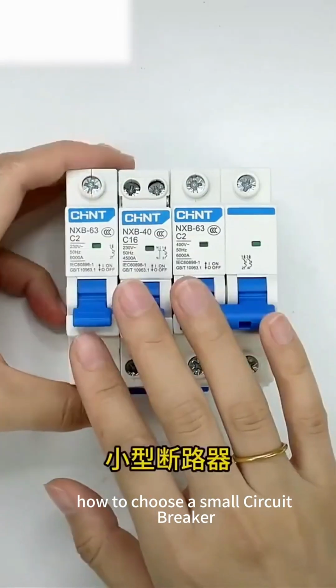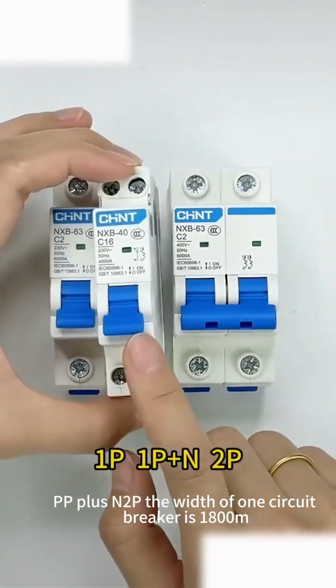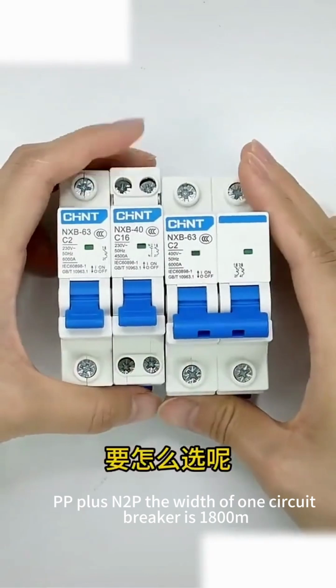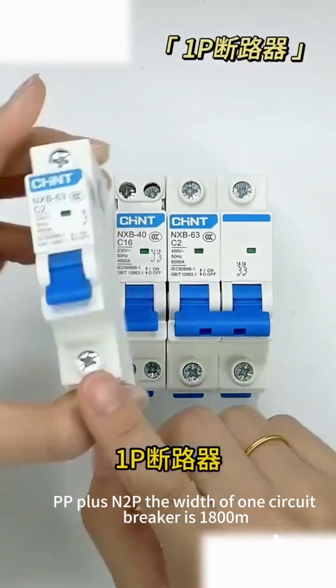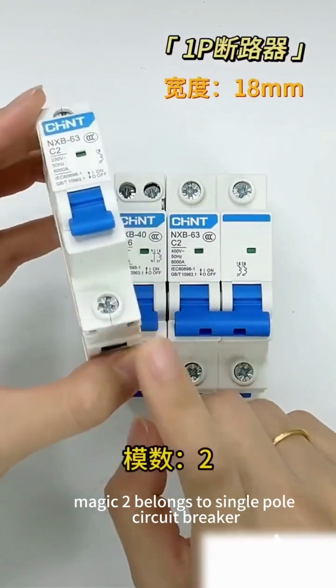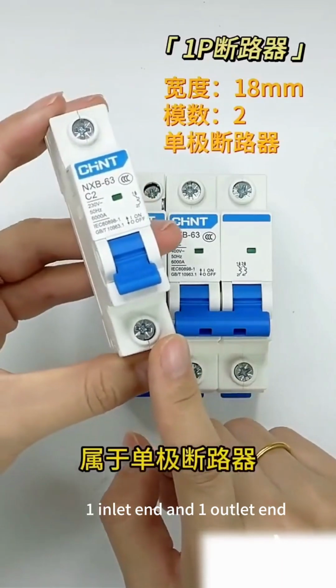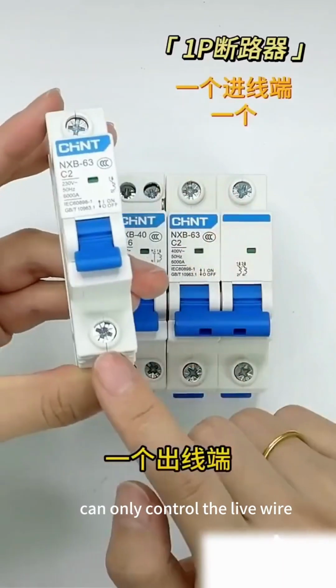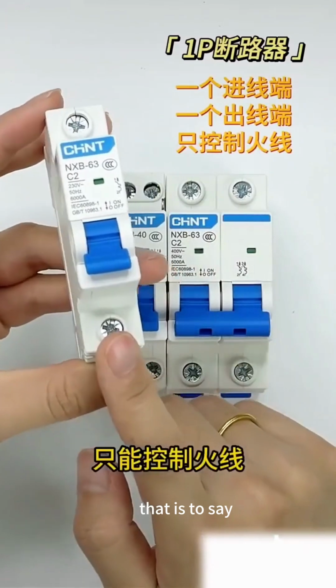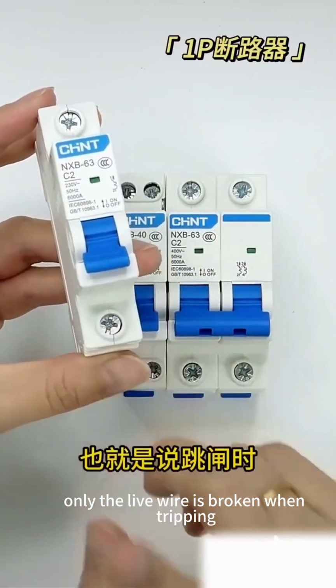How to choose a small circuit breaker: P, P plus N, or 2P. The width of one P circuit breaker is 18 mm. It belongs to the single pole circuit breakers, with one inlet end and one outlet end, and can only control the live wire. That is to say, only the live wire is broken when tripping, while the neutral wire is not.